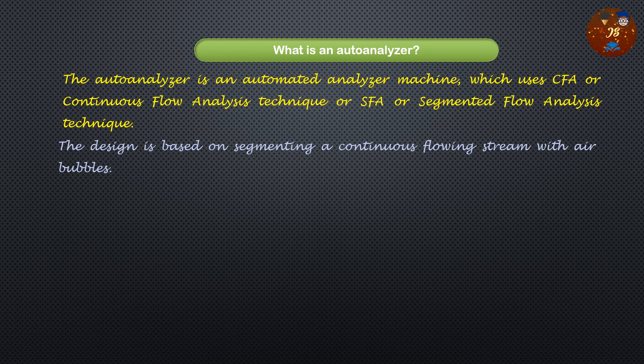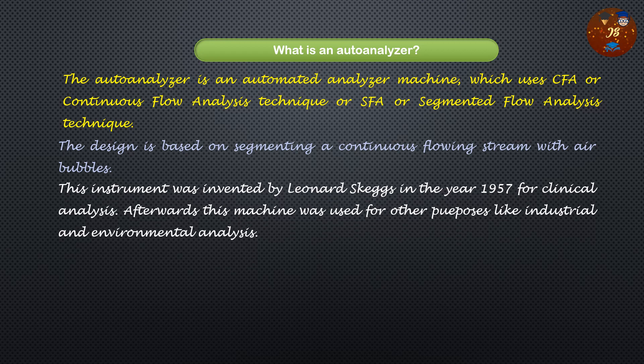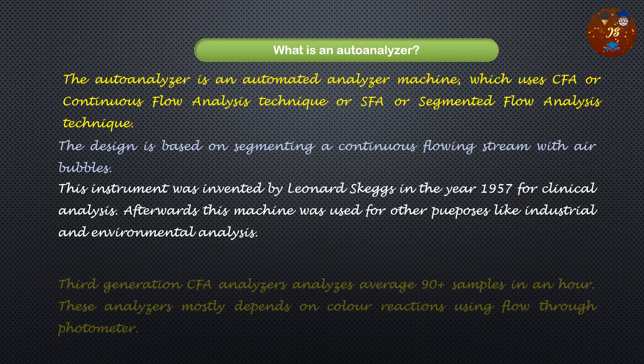The design is based on segmenting a continuous flowing stream with air bubbles — this is the hallmark of the working principle. Air bubbles segment the flowing sample stream into discrete packets, and each packet is dedicated to the analysis of a different thing. This instrument was invented by Leonard Skeggs in 1957 for clinical analysis, and afterwards it was used for industrial and environmental analysis as well.